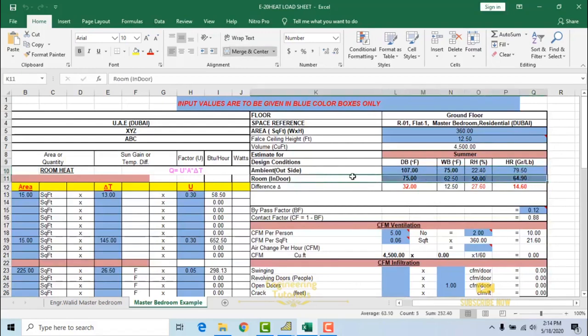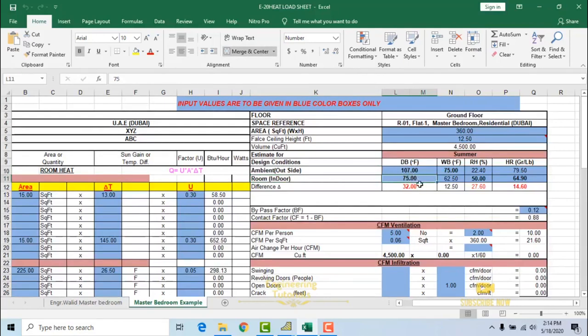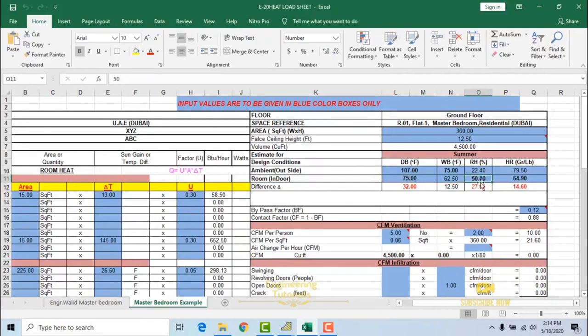Now for the indoor design conditions, for a comfort HVAC system we know that indoor design temperature is from 75 to 78.5 degrees Fahrenheit, so we have selected 75 degrees Fahrenheit. For a comfortable system, indoor design relative humidity is about 50 to 60%, so we have selected 50%. We now need to get the wet bulb temperature and humidity ratio from the psychrometric chart.